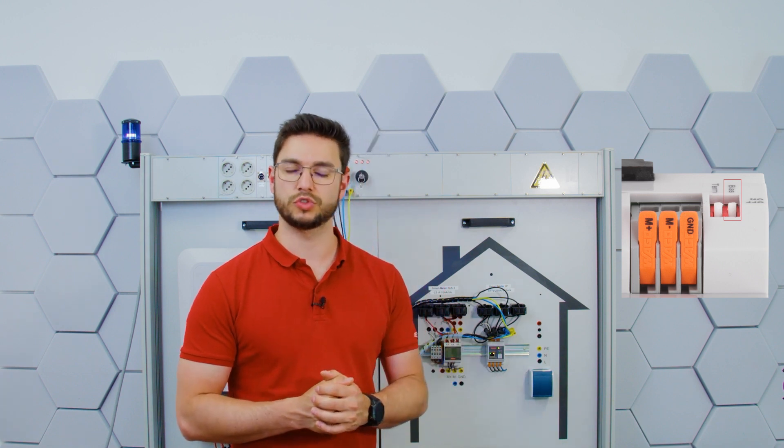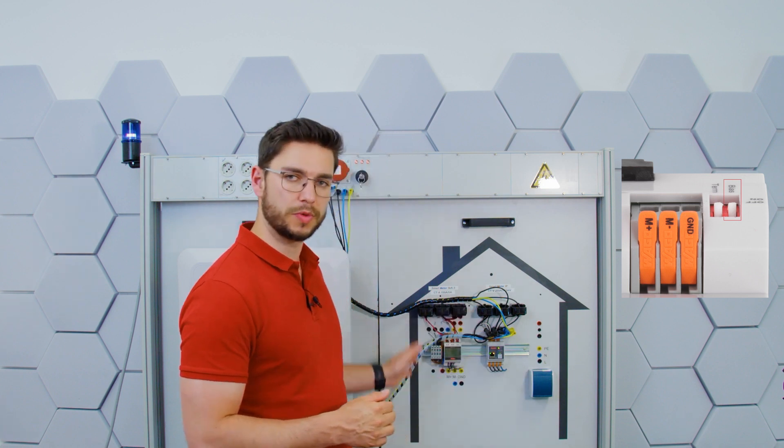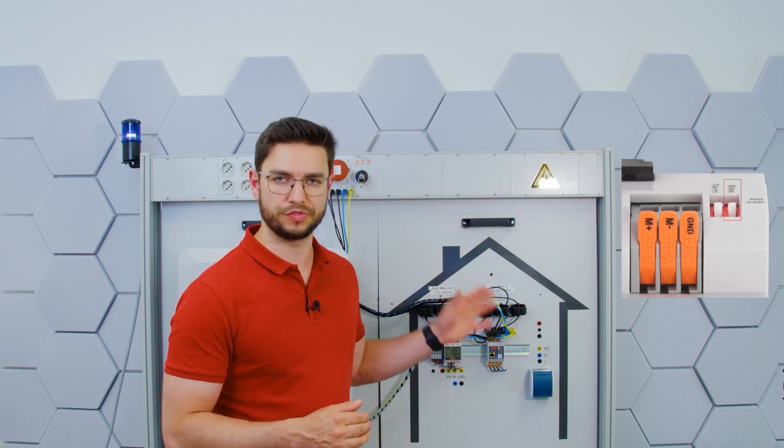And second up, we have the bias switch right next to the termination switch, which is necessary to turn to on position when it's in the Modbus communication together with a Fronius compatible battery. Only then we need to switch it to on. In every other scenario, or when we connect it via LAN or WiFi, we can switch it to the off position. Sounds good.